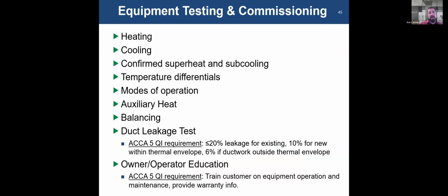What ACCA 5 does is it lays out a procedure, right, and a method of documenting the installation so that you confirm that everything is operational and been set up and working properly, right? So there are checks in there. It tells you that you should be checking the heating, checking the cooling, the modes of operation, confirming your superheat, subcooling, making sure your temperature differentials are within that posted in the manufacturer's submittal.